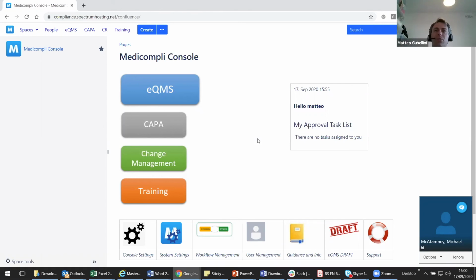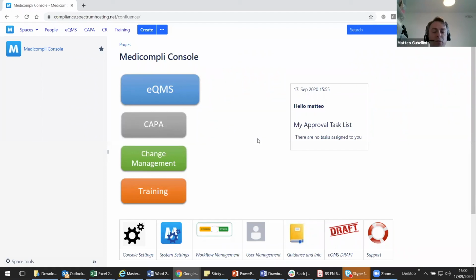What are the things that you have to change? So probably you will have to take a look at the risks, and then you probably have to look at, based on the change in the code, if you have good traceability, and you should have good traceability, you have Jira, say that if I change this button, what are the test cases that I ran when I first released the product that I have to repeat? And probably you will need to add maybe a different test to make sure that the button has a certain size. So, as I said, assuming that you don't need to modify a requirement.